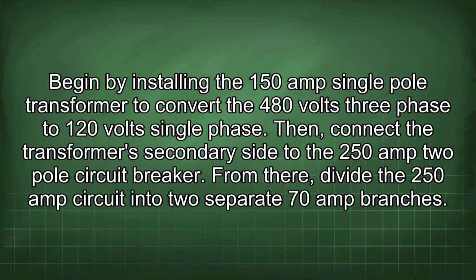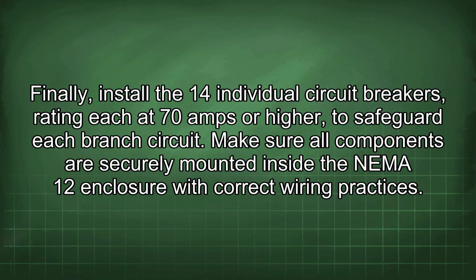Begin by installing the 150 amp single-pole transformer to convert the 480 volts 3-phase to 120 volt single-phase. Then, connect the transformer's secondary side to the 250 amp 2-pole circuit breaker. From there, divide the 250 amp circuit into two separate 70 amp branches. Finally, install the 14 individual circuit breakers, rating each at 70 amps or higher, to safeguard each branch circuit. Make sure all components are securely mounted inside the NEMA 12 enclosure with correct wiring practices.